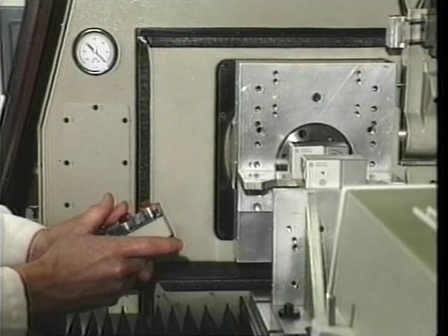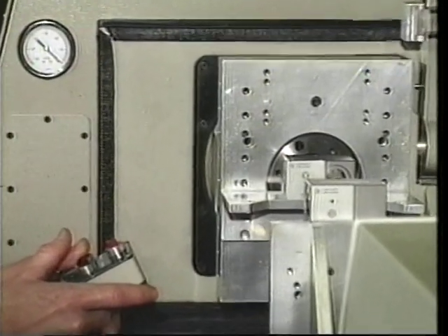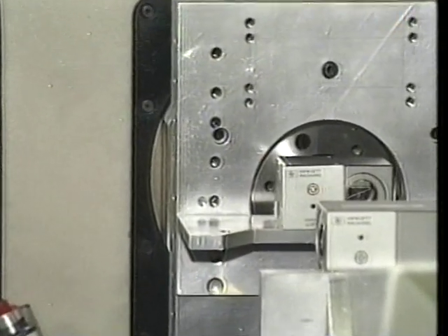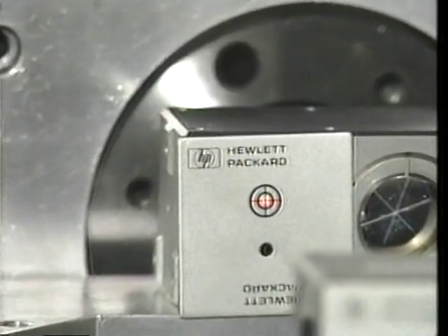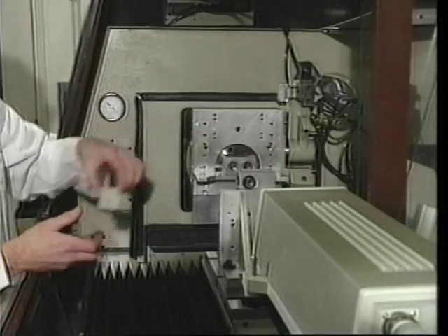If the beam is no longer centered on the reflector target's crosshairs, the laser head is again rotated with the tripod adjustments until the beam is centered on the reflector target's crosshairs. If necessary, the laser head is again translated until the beam is centered with the hole in the interferometer's target. The z-axis carriage is once again jogged away from the interferometer until either the beam nearly moves off the reflector target or the end of travel is reached. When the beam moves away from the center of the reflector target crosshairs, the previously described rotation and translation steps must be repeated.